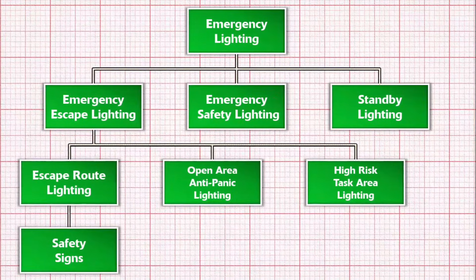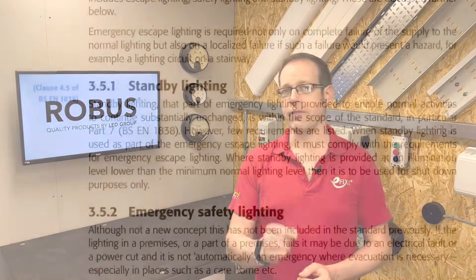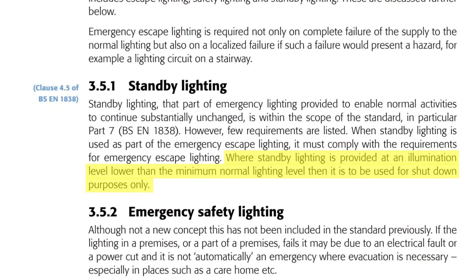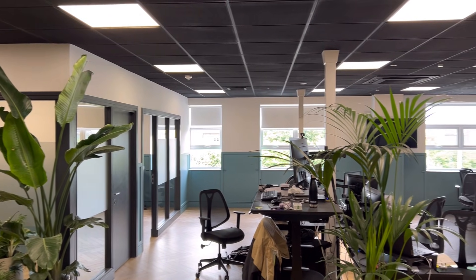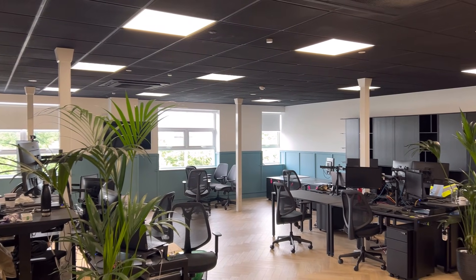Then moving across, we come to standby lighting — separate from emergency escape and emergency safety lighting. It's emergency lighting designed to allow normal activity to continue in the event of general lighting failing, minimising disruption to normal activities. However, if the light levels provided by standby lighting are lower than normal lighting, it should only be used to shut down or terminate processes. It differs from high risk task area lighting as it can be required for less dangerous activities and can be designed to keep activity going rather than just facilitate shutdown. The requirements for standby lighting are also far less stringent and specific.